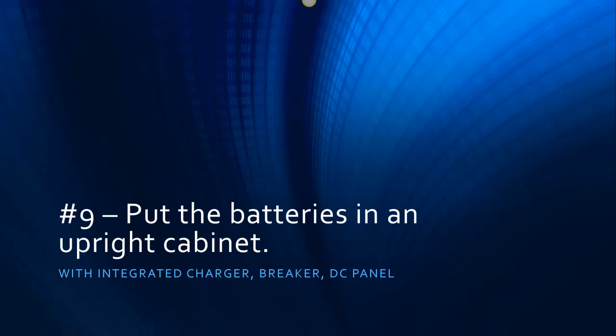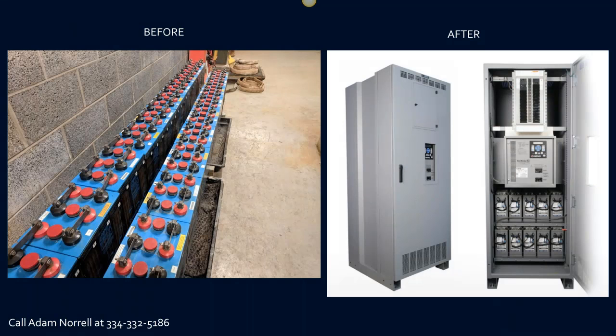Another space-saving design I've run across a few times, or an item that takes up a lot of space in an e-house or an electrical room, are the batteries. On the left is what I'm used to seeing when I walk into a battery room or a switchgear room. I see a rack of batteries and I see spill containment. And it usually takes up 150 inches perhaps of linear space. And these are flooded batteries. And then there's a charger somewhere else.